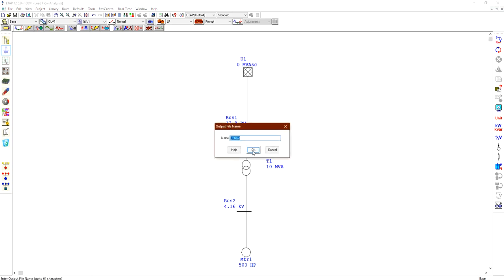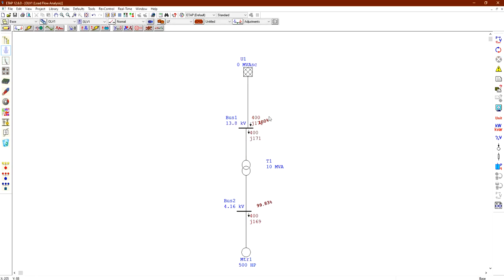Type the name of the output file and click OK. The results are displayed on the diagram. The active power P and reactive power Q are shown for each element. The power absorbed from the grid is 400 + j171 kVA. After the transformer, accounting for losses, the power entering the motor is 400 + j169 kVA, which drives the induction motor to deliver 500 horsepower of mechanical output power. This concludes a simple example of load flow analysis in ETAP.